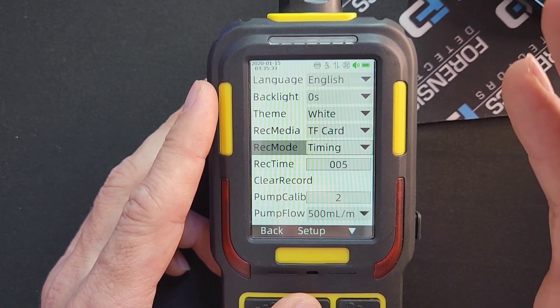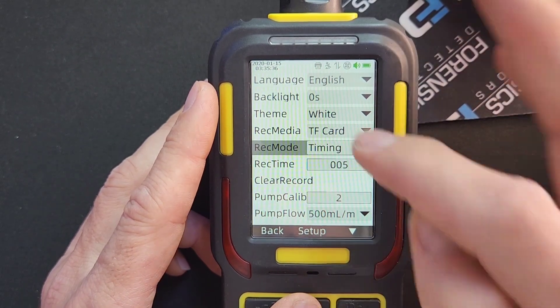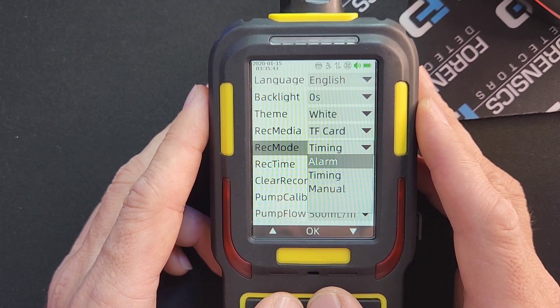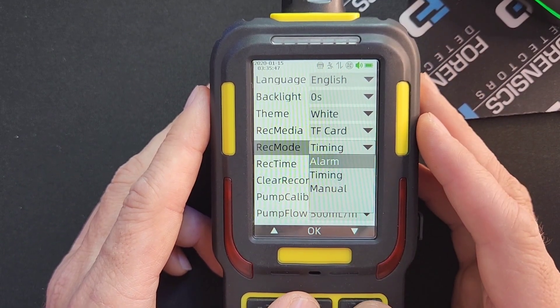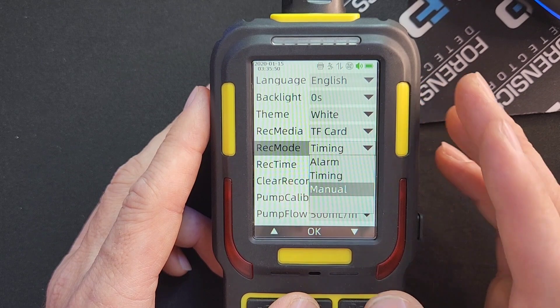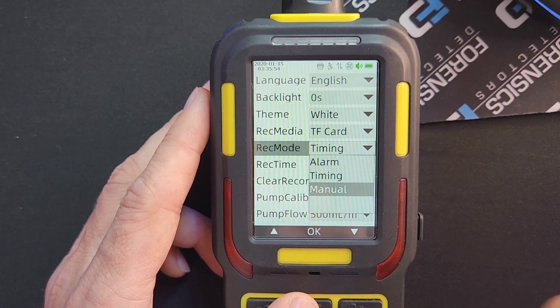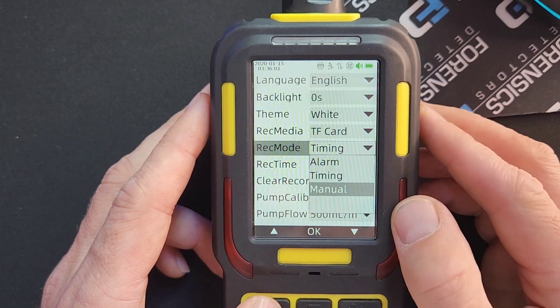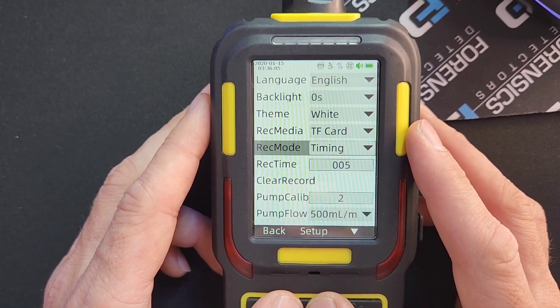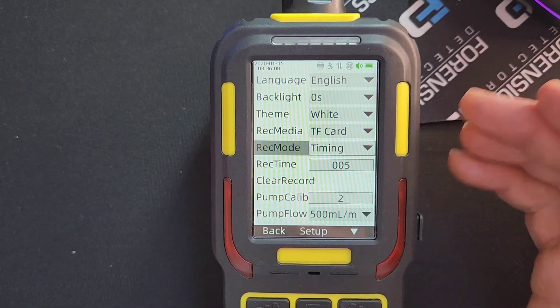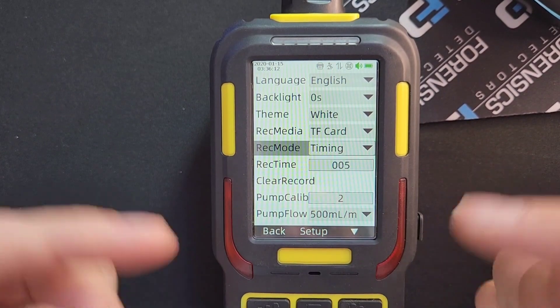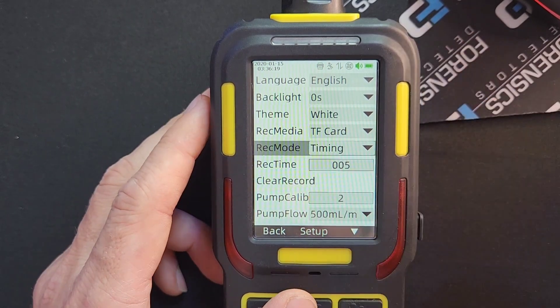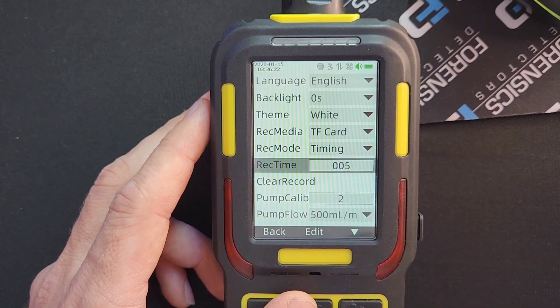If you want to record on a periodic basis, select Timing mode. If you want it to only record when an alarm event occurs, select Alarm. If you want to record manually at a specific time when you tell it to take a data point, select Manual. In most cases customers typically want Timing — you leave the unit running for a period of time, maybe one hour, two hours, or one day, and it records the gas levels into memory for you to download later. So set it to Timing.